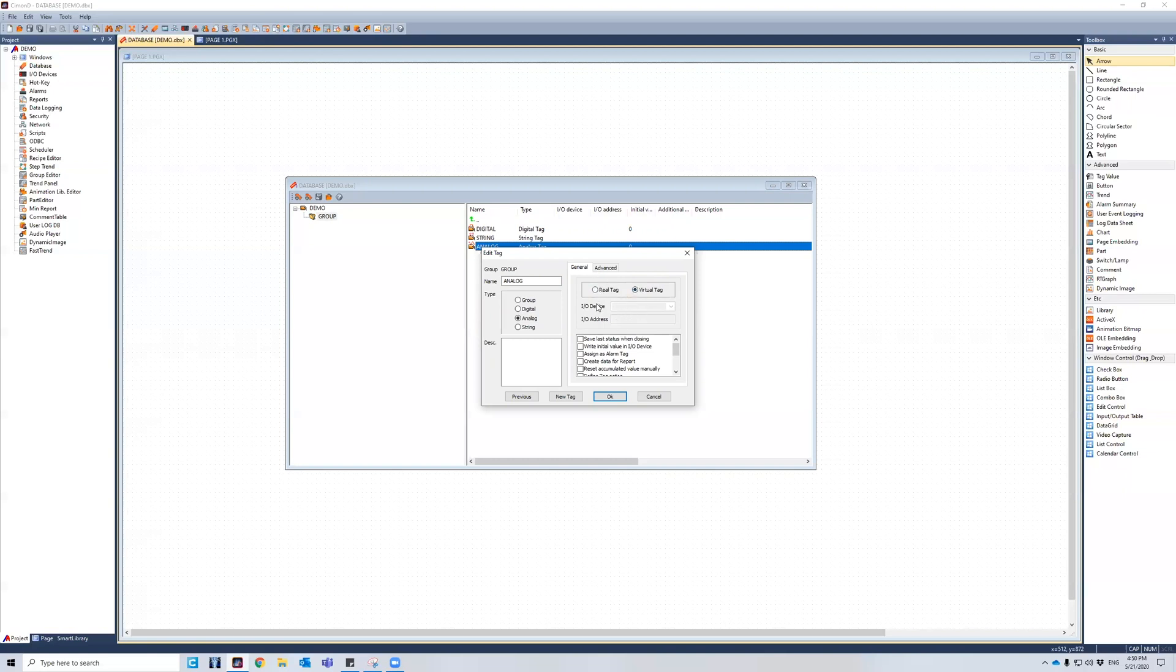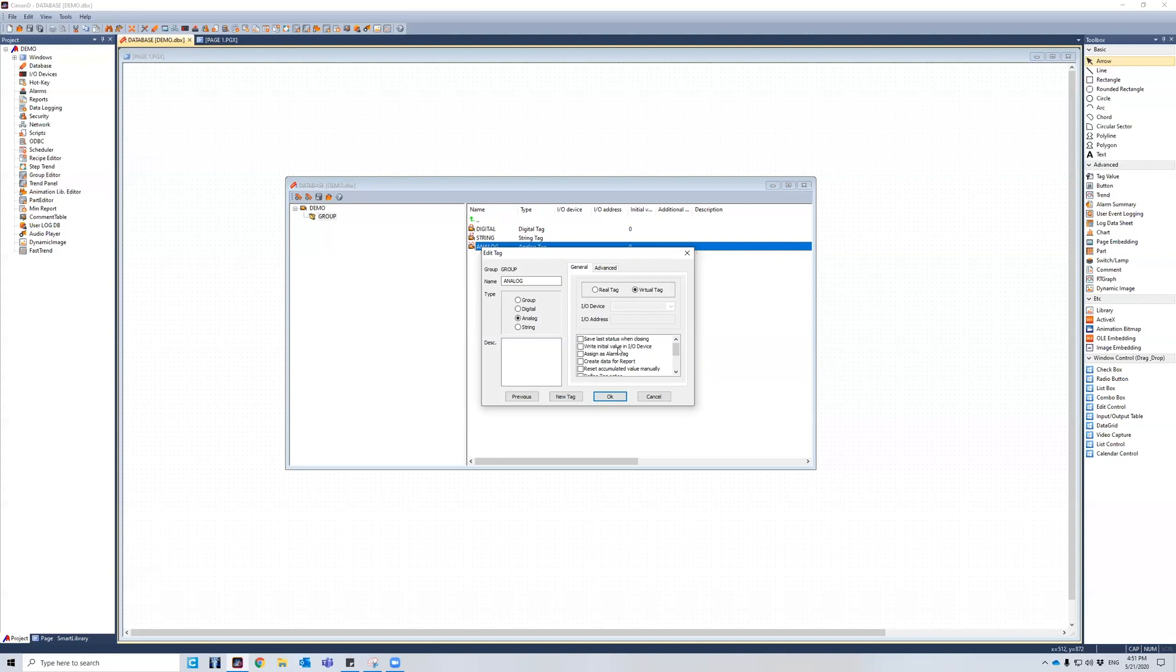Furthermore, let's go into the parameters of analog. So you'll see down here, we can save last status when closing, making it retentive. We can write initial value into an IO device, which would be like a cold initialization onto IO devices. And then you can see here, we can also assign an alarm tag. So this is how you would assign an alarm to any type of tag. And then you can tell it to go off at a certain given time.